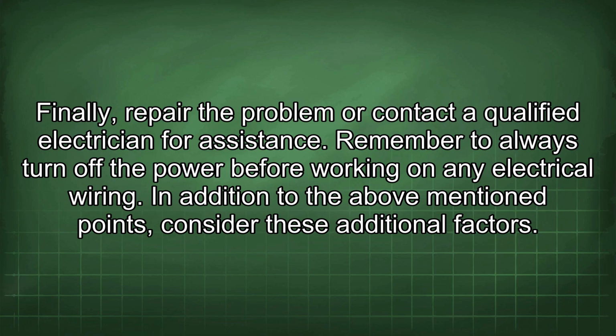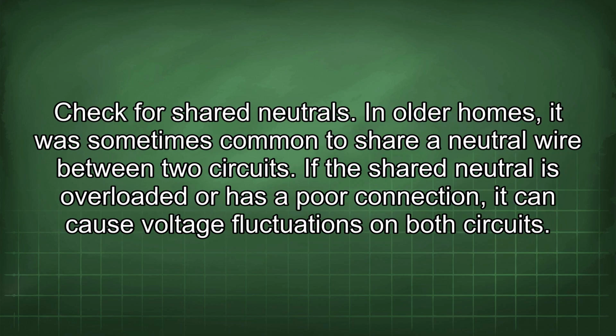In addition to the above-mentioned points, consider these additional factors. Check for shared neutrals. In older homes, it was sometimes common to share a neutral wire between 2 circuits. If the shared neutral is overloaded or has a poor connection, it can cause voltage fluctuations on both circuits.